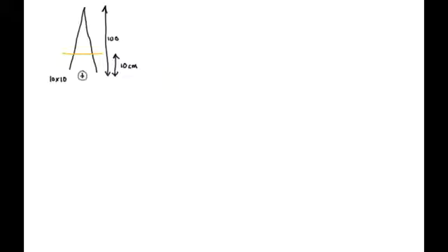So let's start by looking at the setup for a TG51 measurement. You're going to set up at 100 centimeters to the isocenter and at a depth of 10 centimeters, and it's a 10 by 10 field. And then the chamber goes here at that depth. That's where the measurement is made. Now, you're going to measure a charge in that chamber, Q, and then, like I said before, the goal is to convert that to a dose in water.